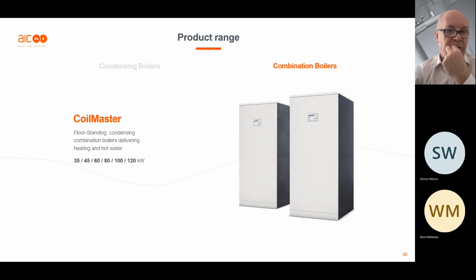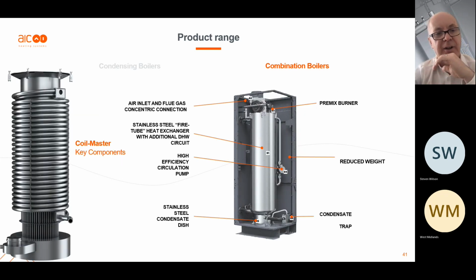Okay, and then we have our flagship product, which is the Coil Master, which is a water heater that also does your heating if required. So again, it goes from 35 up to 120 kilowatts. Okay, so you can see internally here we've got the same theme running throughout with the stainless steel, no mechanical joints. On the left hand side, you can see the FireTube running in the middle of the domestic hot water coil. Okay, so domestic hot water goes through that stainless steel coil, so it's an instantaneous water heater that also does your heating. Okay, so if you look at that unit there, the 120 kilowatt, using the FireTube technology, can produce over 1,800 litres every hour of hot water at 60 degrees. Okay, from a very small footprint.